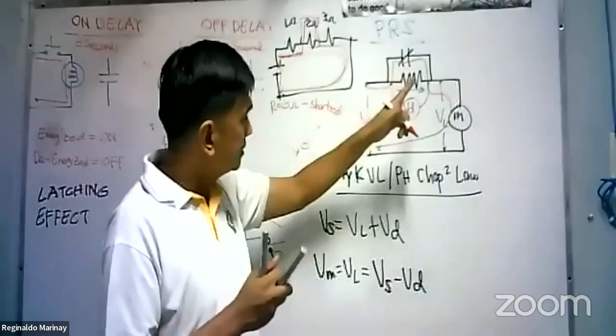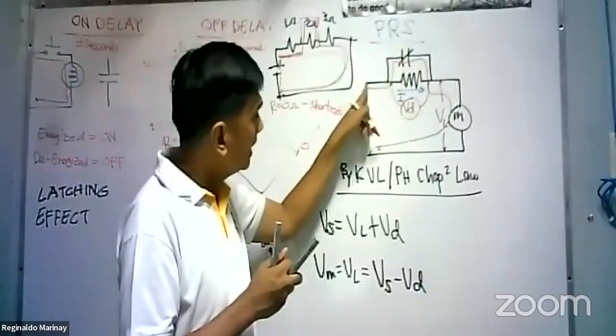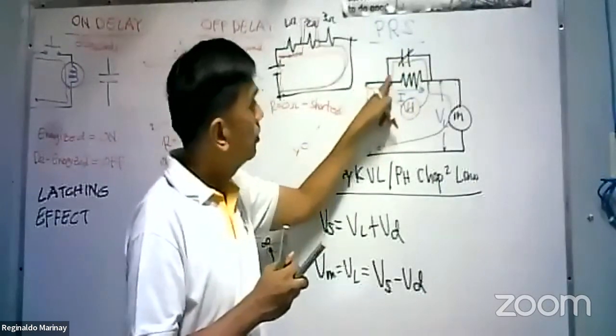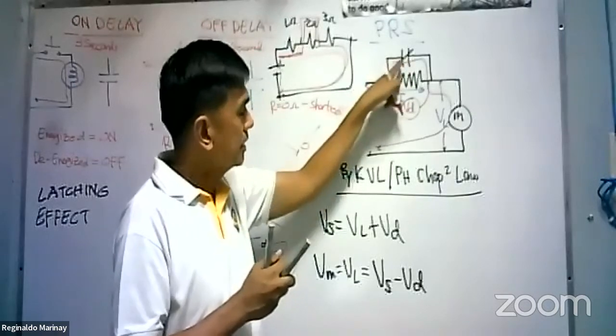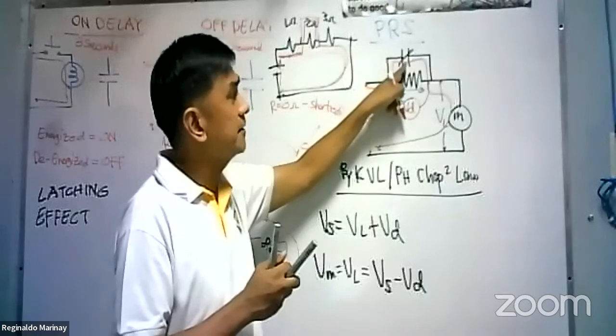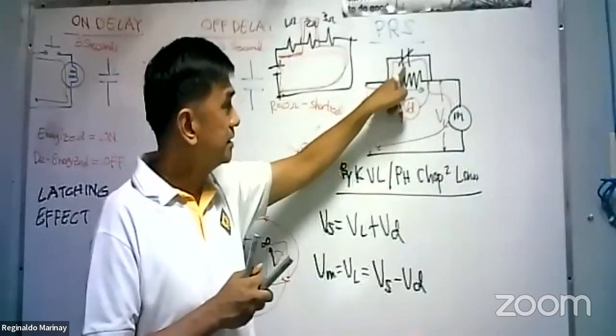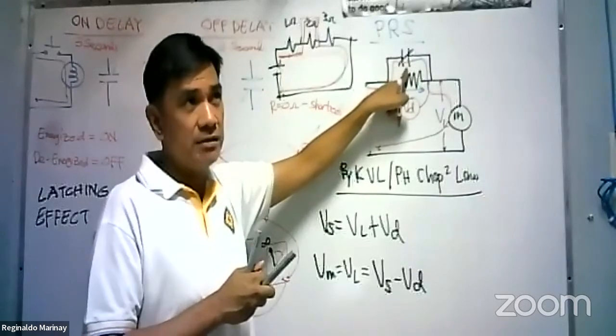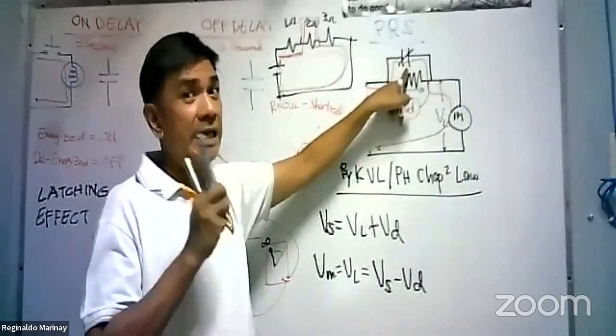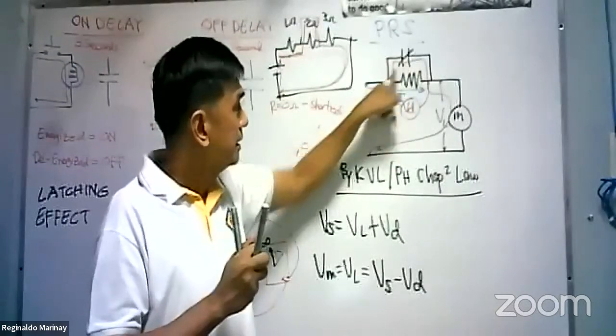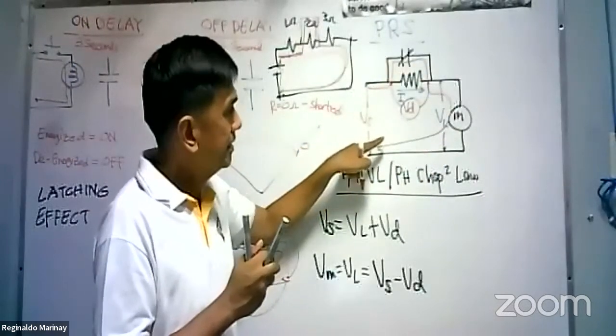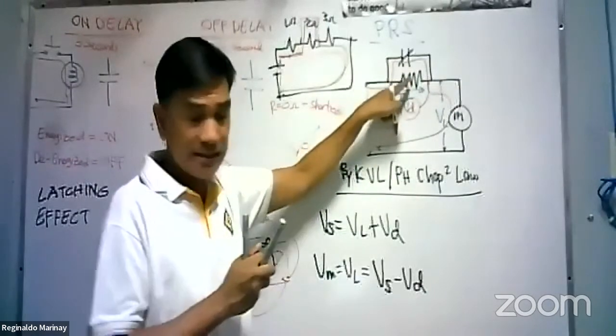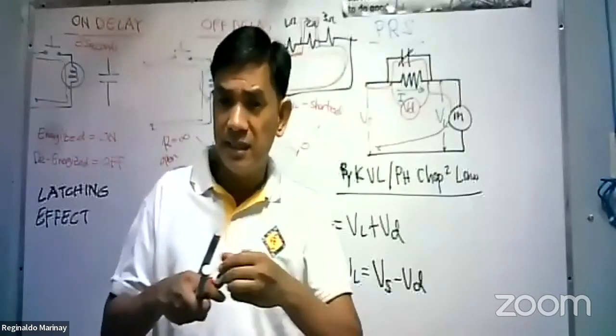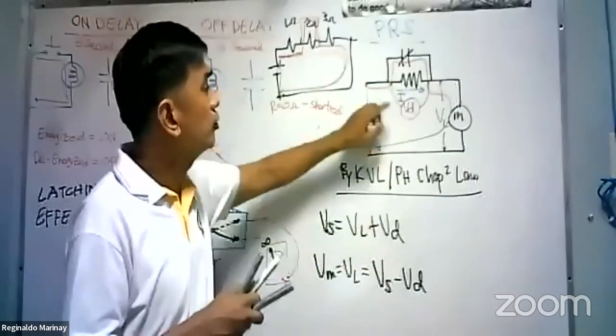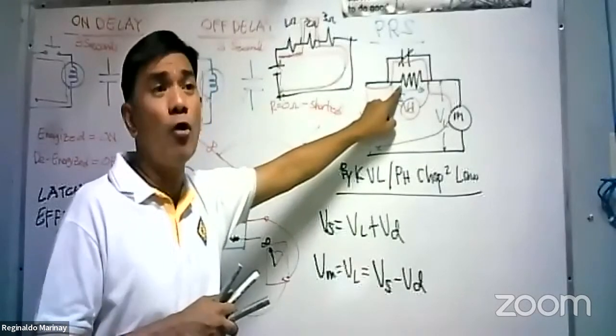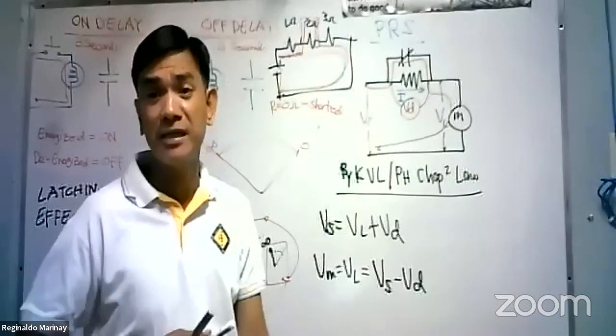Now, in the primary resistance starter, once this becomes a closed path, all the current here will go to the normally closed. Actually, this is normally open, held closed. Once you read this, this is what we call normally open held closed. It was held closed. The current will flow here, then go into the motor. You see, the current will no longer flow to your resistance unit. If you have a 3-second setting, let's say 1, 2, 3, you're going to use this resistance unit for only from 0 to 2.99 seconds.